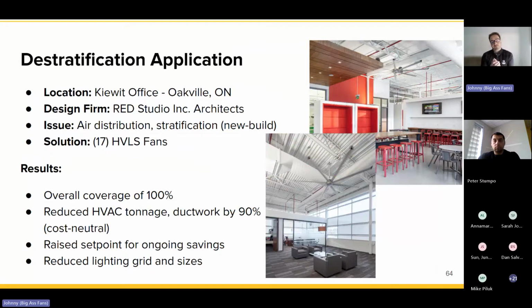So how do we apply this? Just some more local examples. Kiewit, their office in Oakville, we worked with Red Studio Architects to design a system that reduced the amount of tonnage and redundant legs of ductwork in their space. We used 17 commercial fans, you can see them in the image there. They relatively blend with the space, and overall we were able to reduce their tonnage and ductwork by about 90%. Coverage as far as distribution of the air stayed the same, but we reduced the amount of redundancies in their system significantly.